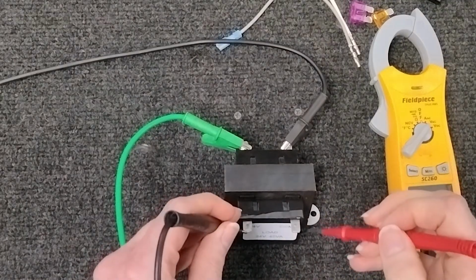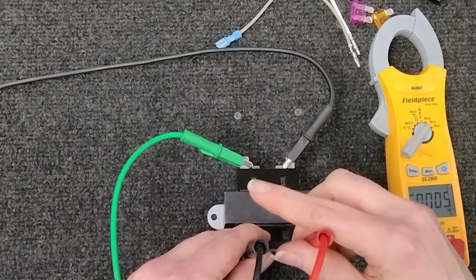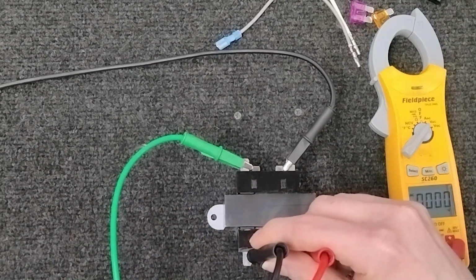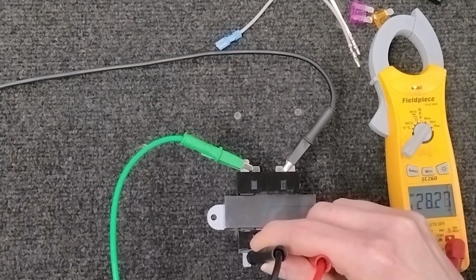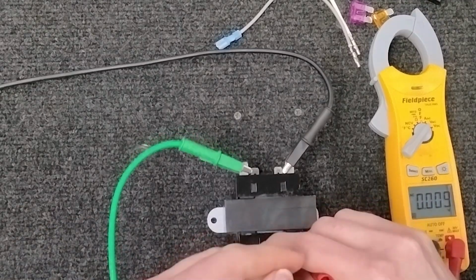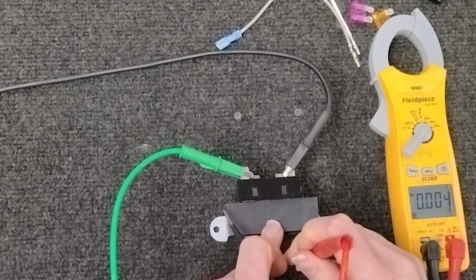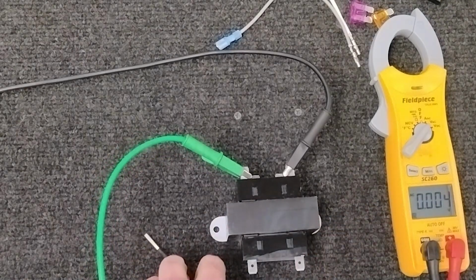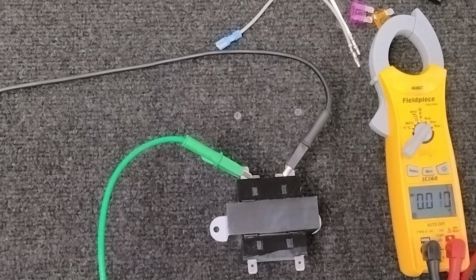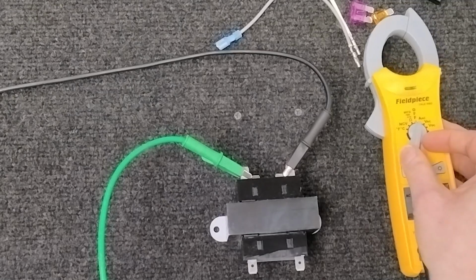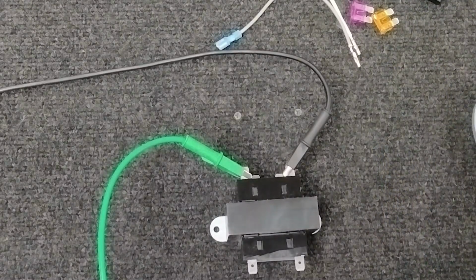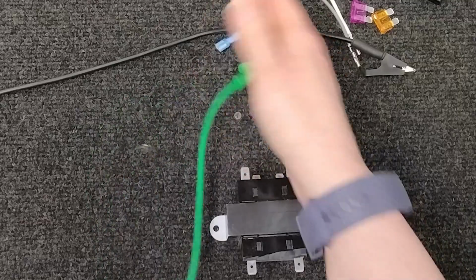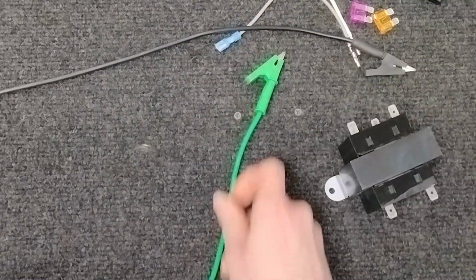But this is where, again, we're going to put one lead on each. We're going to turn on our power, and there you go. Should be between 26 to 28 volts. So always make sure you've got power coming into your unit before assuming that something could be going on with your control board. And a lot of people like to jump to the control board as being the culprit. So now that we know this is okay, or we've stopped there and we know that, hey, I'm not getting power, or my transformer is not working, how do we check and make sure that it's not our board?